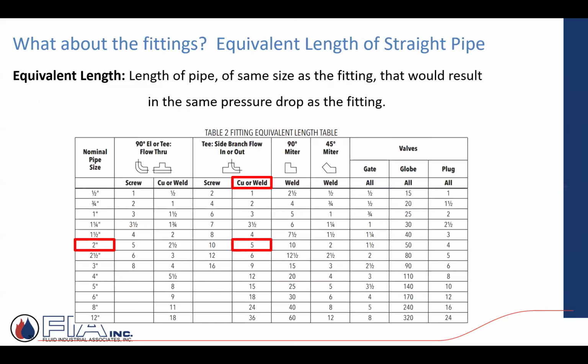1,000 feet or whatever the number is. One other thing to be aware of, which again, software a lot of times takes care of, is fittings. Fittings offer a certain pipe equivalent length, a TEL they'll call it. So as a quick example here, if I was just to highlight a 2-inch T with a side branch in or out, I'm saying that a 2-inch T has the equivalent length of 5 feet of piping. So 1 T would be like having 5 feet of pipe.